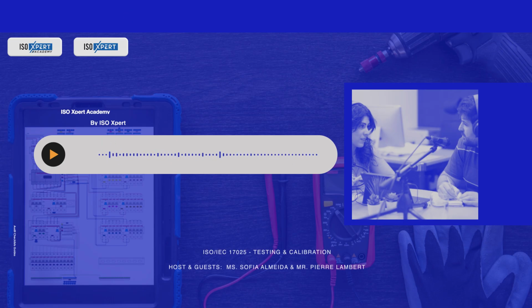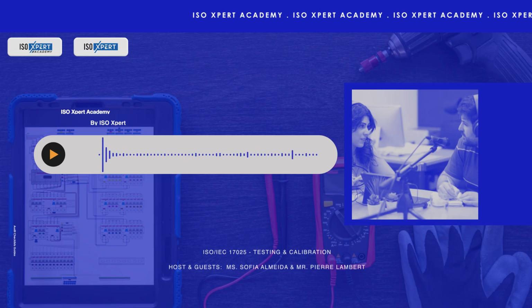So not just papering over the cracks. Precisely. Auditors would expect to see those improvement logs we mentioned, the CARs, corrective action requests, and detailed root cause analysis reports. This demonstrates that the lab truly understands why an issue occurred and has put measures in place to ensure it won't be repeated. It's a learning loop.